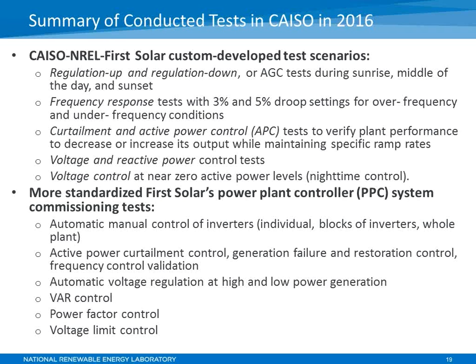So this is an example of one day of testing. There are several hours of test data as measured by the PMU units at the plant high voltage terminals. So these are active and reactive power control time series. And the yellow one on the top is the actual voltage as measured at 230 kilovolts. As you can see, this is not the typical production profile that people expect from a PV plant, simply because we're conducting many tests during this particular day and consecutive days.